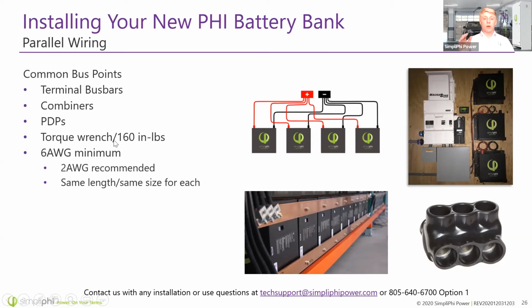Now last but not least, I want to stress that a torque wrench is definitely needed for installing our batteries. A socket wrench can often lead to over-tightening and maybe stripping the terminals, or I've even seen lately people snap off a terminal completely because they tightened it too tight with a socket wrench. They weren't knowing what the torque was. Maybe they even had their torque wrench in a metric setting, I'm not sure, but make sure to use 160 inch-pounds to tighten the nuts on the terminals.